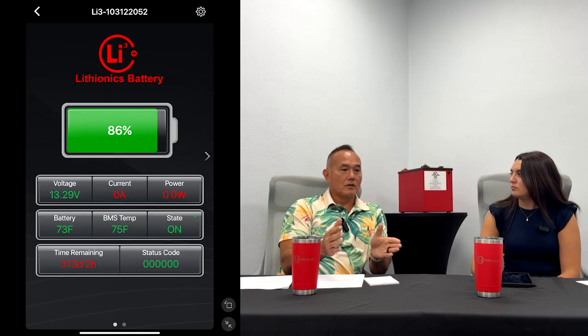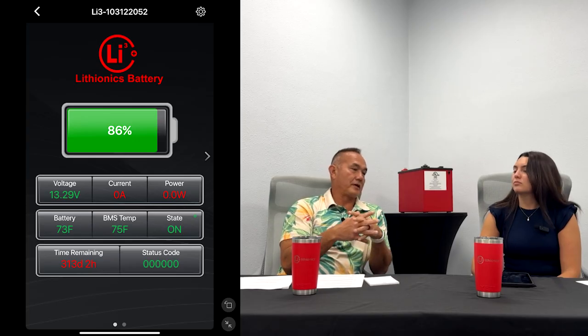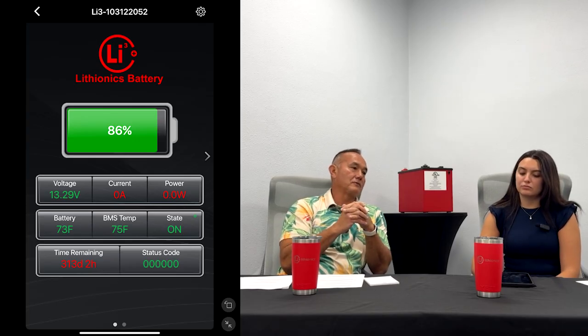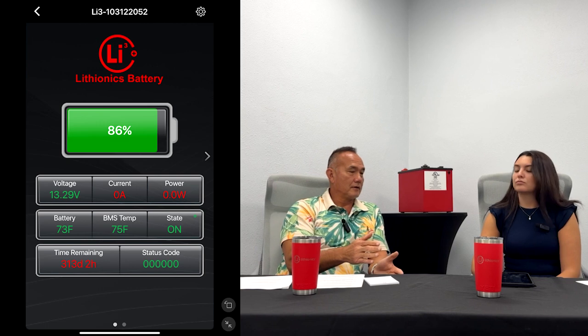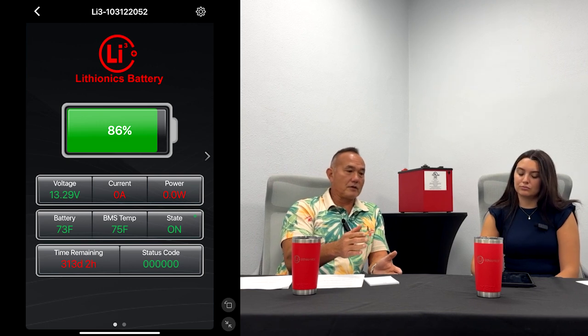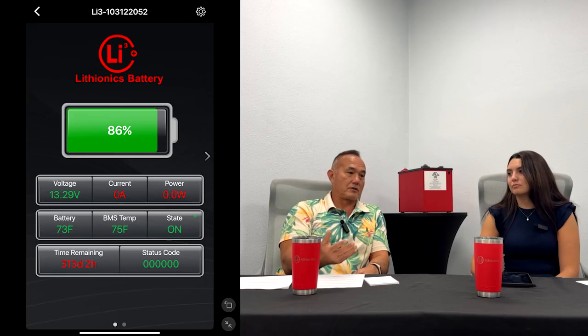There's a recommended no-lower-than discharge rate. We have a couple of thresholds: one's called reserve voltage cutoff, and we also have another threshold called low voltage cutoff. Your BMS is going to protect you. If you hit the reserve voltage level, the BMS automatically shuts off to protect the battery, and you need to start charging at this point. Stop using your battery and start charging.